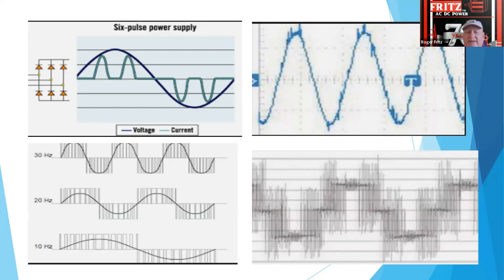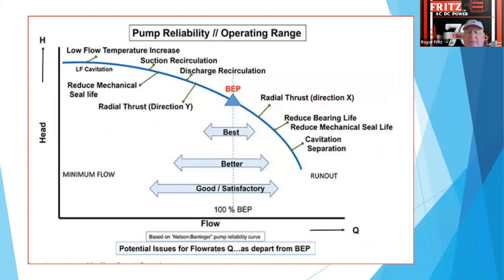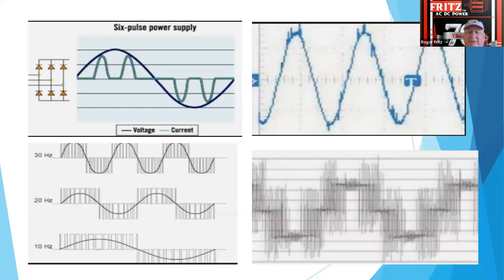When we slow it down to like 30 hertz, the motor will literally run half speed, and depending on where we're at on the pump curve, and also the cube factor of horsepower, you'll end up saving in terms of power. So at 30 hertz on a pump, you'll be running half speed, so you get about half the flow, but it's a cube factor, so it's 0.5 times 0.5 times 0.5. So the actual horsepower is only 1/8 of the amount running half the flow.